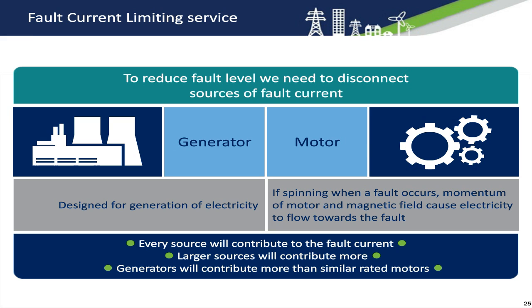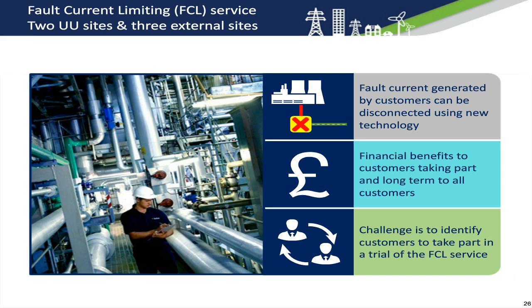Fault current limit service enables us to disconnect the fault current generated by industrial, commercial and generation customers using new technology which will be trialled under the Respond project. This commercial solution will enable customers to earn rewards and will benefit all distribution customers through reduced reinforcement costs. We believe there is significant equipment out there that is contributing to fault current that can be part of the solution. Our challenge is to identify customers who have such equipment, engage with these customers to explain Respond and see if and how they can contribute.